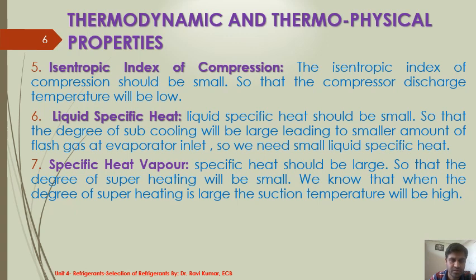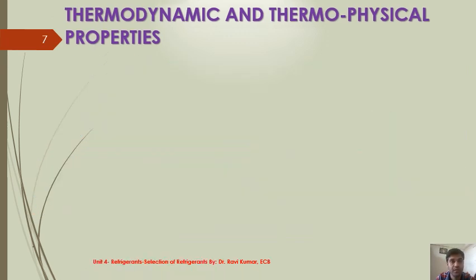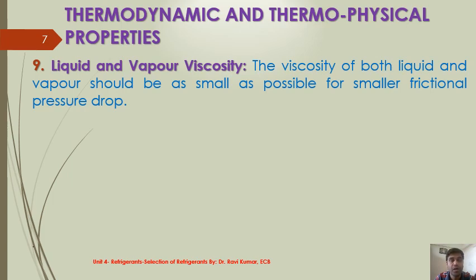When the degree of superheating is large, the suction temperature will be high. Once the suction temperature is high, the density of the refrigerant at the entry to the compressor will be low, meaning a larger compressor is required for a given mass flow rate. So we should have a high value of vapor specific heat, but the liquid specific heat should be low — again, these are contradictory requirements. Both liquid and vapor thermal conductivity should be as high as possible for higher heat transfer coefficients. The viscosity of both liquid and vapor should be as small as possible for smaller frictional pressure drop.